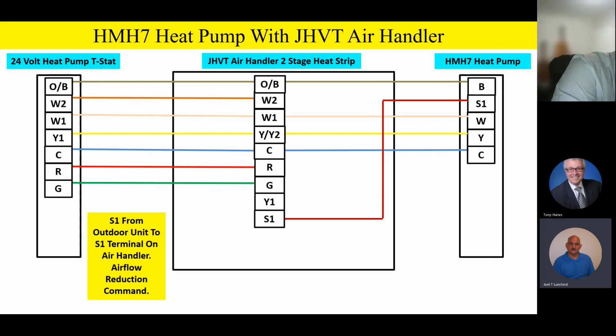If you take a look at the install guide, it's very, very clear on how to set up that S1 input. So one more time, the S1 input is a direct input from the outdoor unit to the indoor unit on the JHVT air handler for airflow reduction. You do not need that relay kit. However, we have to make sure we set it up like we talked about in the previous slide. The AC HP switch has to be in the heat pump position.